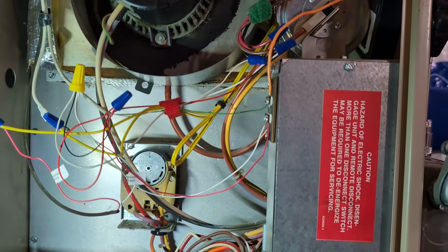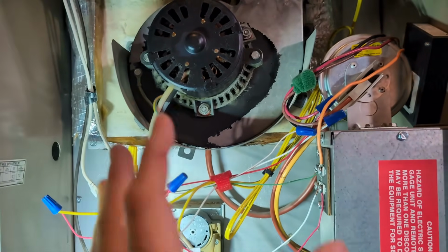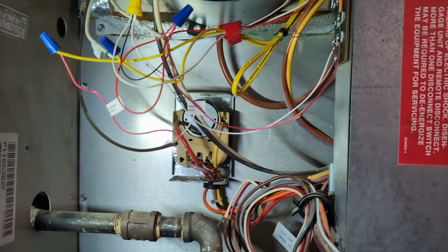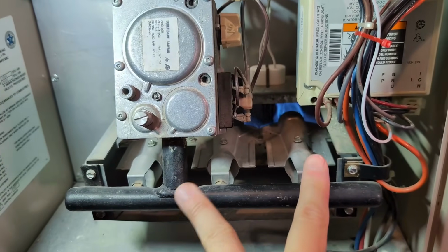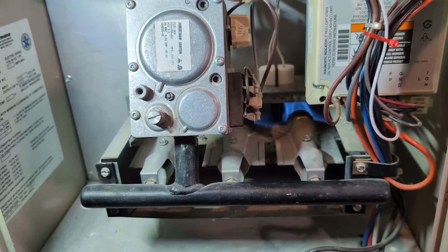So yeah, there's probably a few other parts I should get. This here is a pressure sensor, I think, for air pressure stuff. And that is the thermal cutout switch. That thing on the back there, those can go bad too. They're just less of a wear item. Obviously, the two things that are in the flames get a lot more exposure to the elements, and therefore they are super unhappy.